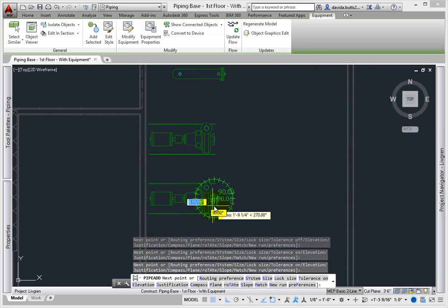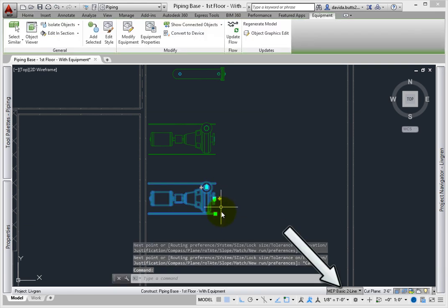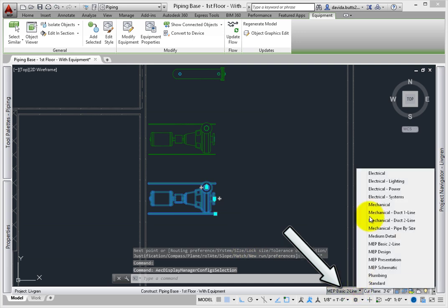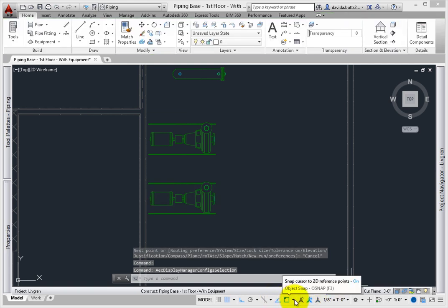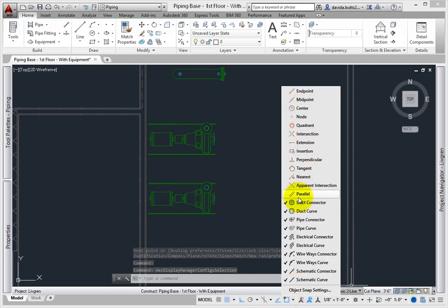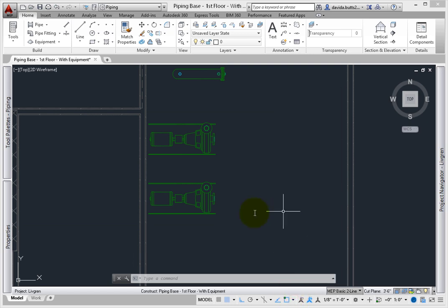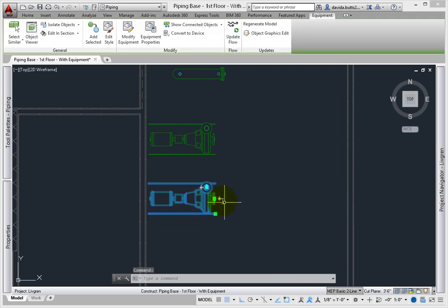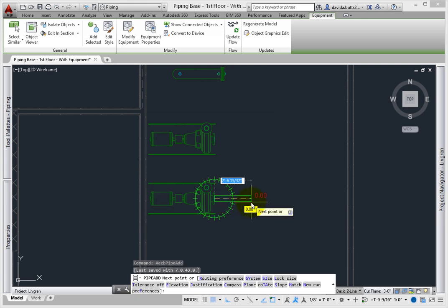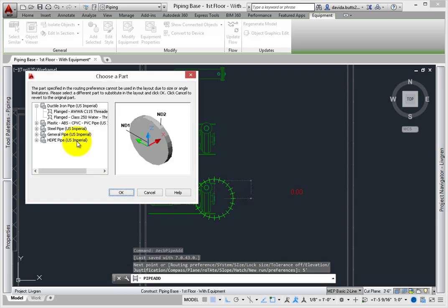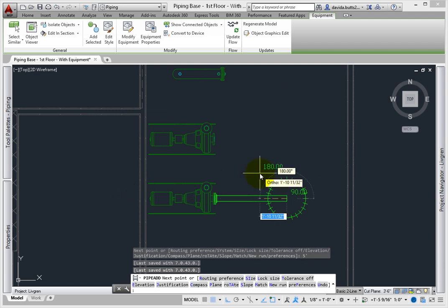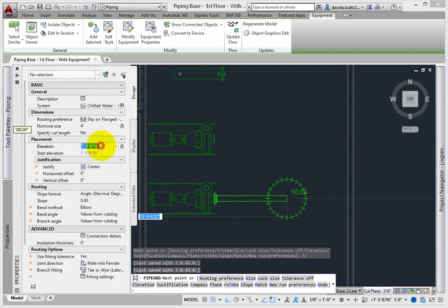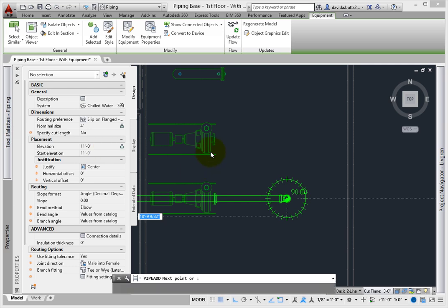Select OK to continue. Next, add piping from the pumps to the chiller. Set the display to MEP Basic 2 lines so the whole pipe displays. Before you create the pipe, go to O-snap settings and turn off the AutoCAD snaps, leaving the MEP snaps turned on. Start by picking the grip on the suction face of the lower pump. Since you don't want to place the suction diffuser, draw a 5-foot-long pipe segment. Next, change the elevation to 11 feet and press Enter — the riser is automatically created based on the pipe preference setting.